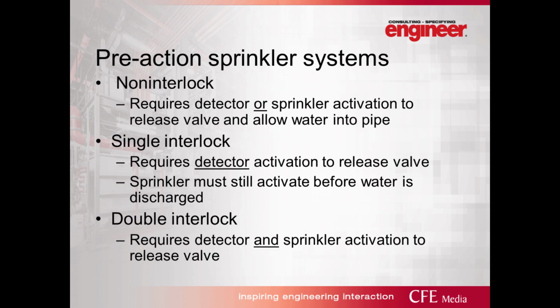There are several different types of pre-action sprinkler systems. There's a non-interlock, which I personally have never seen anyone use, which basically just requires either a detector or the sprinkler to activate to release the pre-action valve and allow water into the pipe. Again, there's not a lot of fail-safe with this type of non-interlock system, so it's usually not used because it fairly well mimics a wet sprinkler system for the most part.